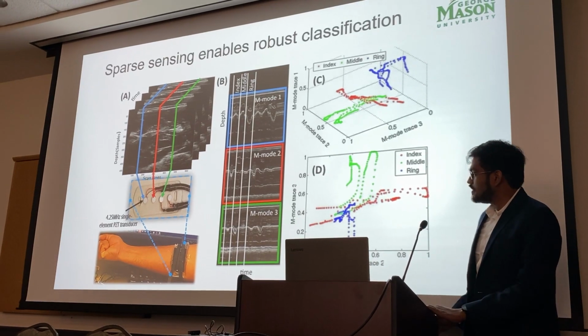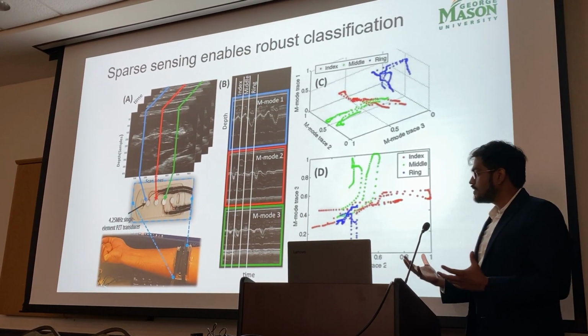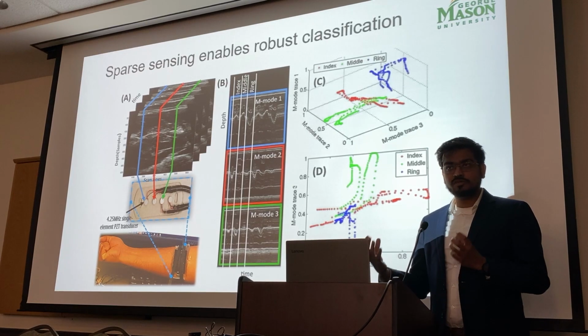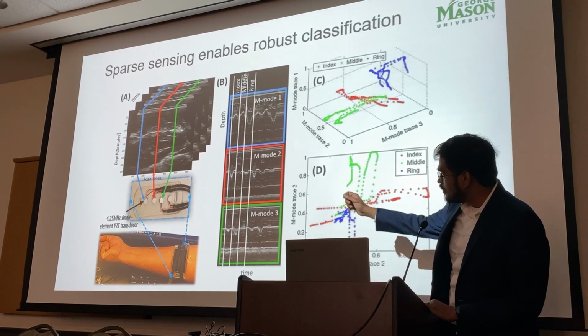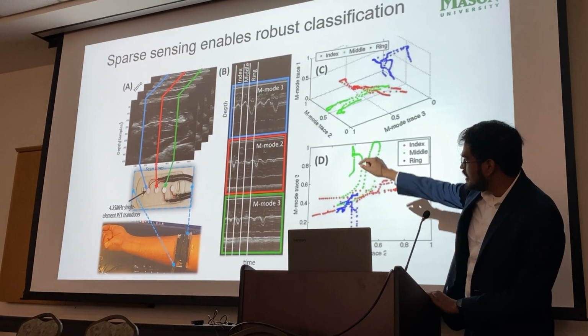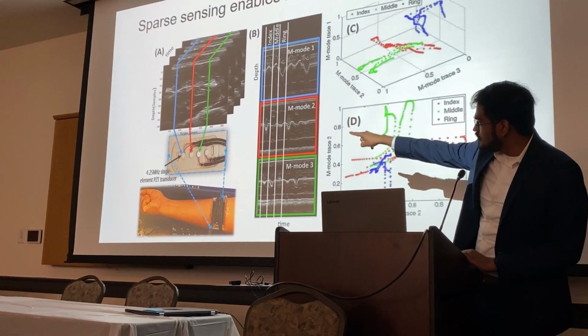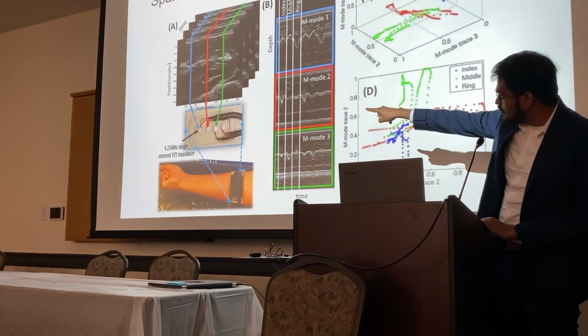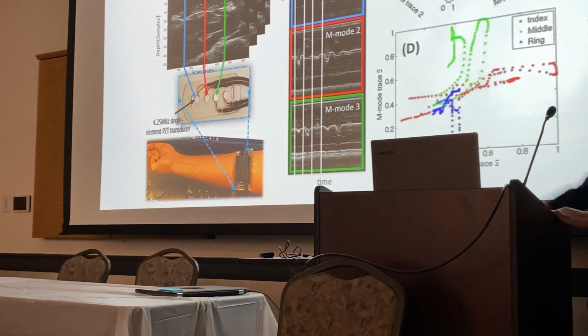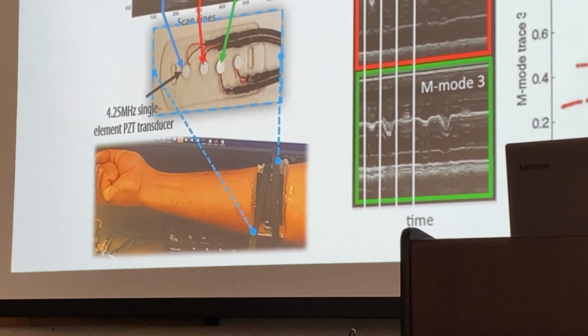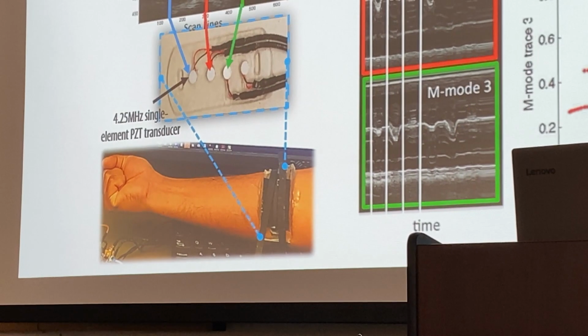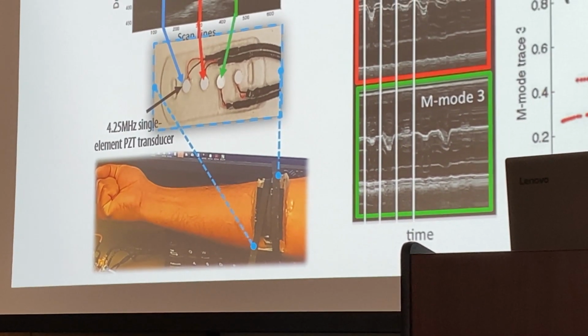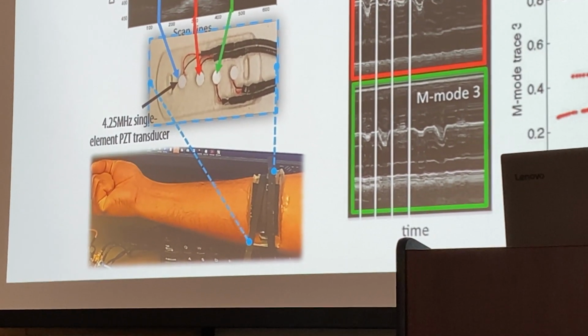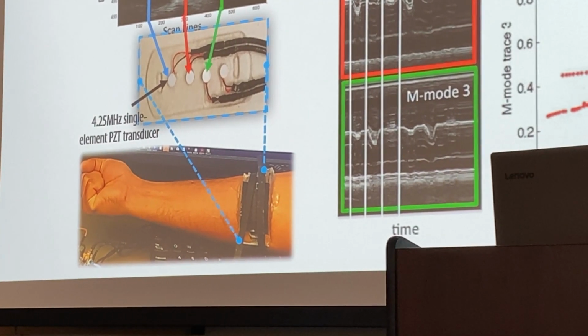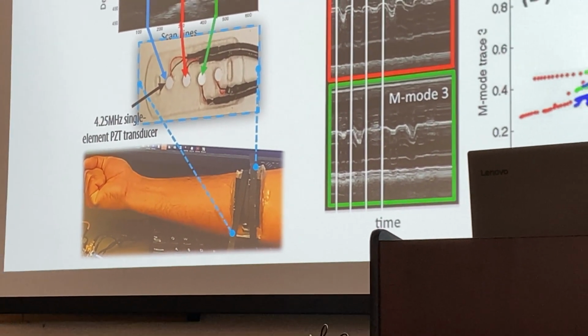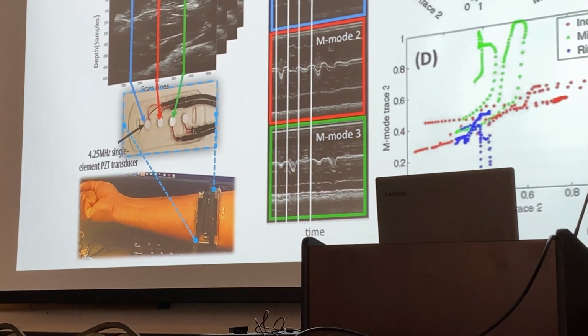So from there on, what we did was we developed wearable ultrasound transducer patches. On the left-hand corner, what you see is one ultrasound transducer, which would be that white dot in between. Each of these elements can be excited electrically, and they would emit sound into the body. So we have 4 such elements. I've only shown 3 here, but there are 4 elements over there. And this is placed on a flexible silicone-based patch.